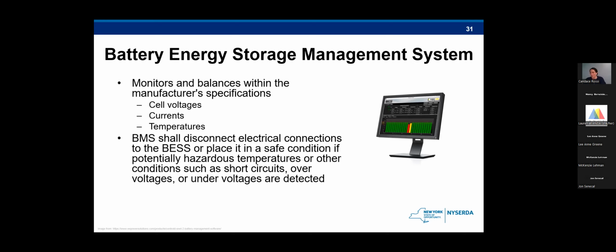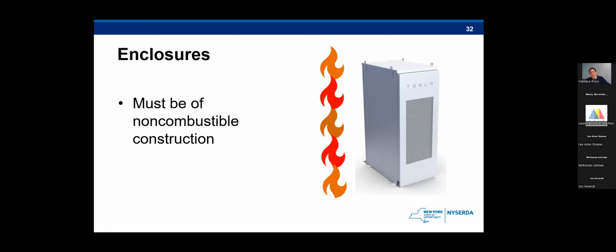So where required by the energy storage system listing, an approved energy storage management system that monitors and balances cell voltages, currents, and temperatures within the manufacturer's specification. The system shall also disconnect any electrical connections to the energy storage system or otherwise place it in a safe condition if potential hazardous temperatures or other conditions such as short circuits or over voltage or under voltage are detected. So here we have the enclosures. All energy storage enclosures should be made of non-combustible material, and this is to contain the fire within the enclosure, if there is one, so that the heat does not transfer to other enclosures.